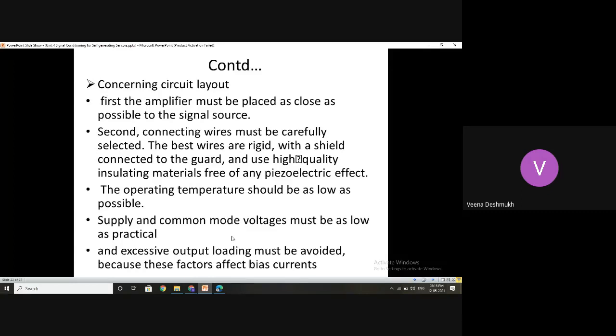Excessive output loading must be avoided. This is usually handled by taking care of how many components can be connected. So excessive connections are not allowed. If you want additional connections, the same care taken now has to be taken with the elements or components you are using. Excessive output loading must be avoided because these factors affect bias currents, and once bias currents are affected, the entire electrometer functioning gets affected.